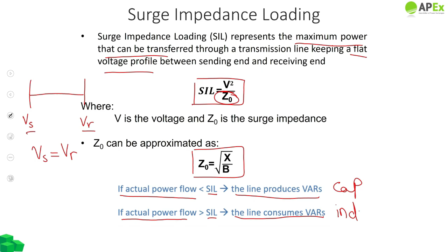Once we find Z naught based on a particular voltage, we can find the surge impedance loading. To restate a key point: if the actual power flow is less than the surge impedance loading, the line produces vars and acts like a capacitor. But when the actual flow is greater than the surge impedance loading, the line consumes vars and acts like an inductor.